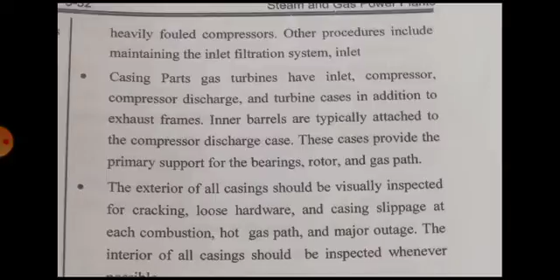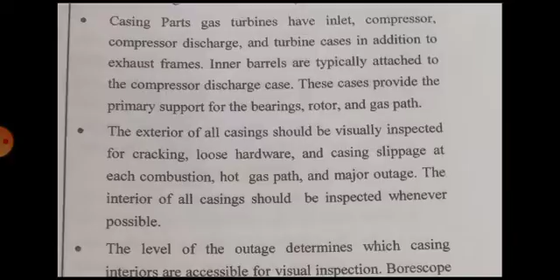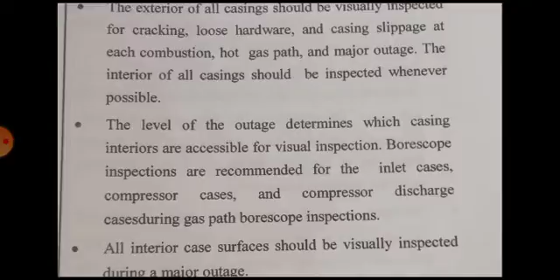Casing parts: gas turbines have inlet, compressor, compressor discharge, and turbine cases in addition to the exhaust frame. Inner barrels are typically attached to the compressor discharge case. These cases provide the primary support for the bearings, rotor, and gas path. The exterior of all casings should be visually inspected for cracking, loose hardware, and casing slippage at each combustion, hot gas path, and major outage.